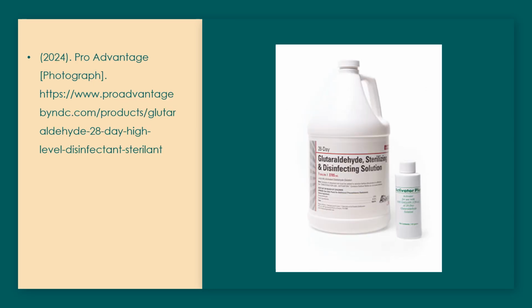Glutaraldehyde is another solution that is commonly used in cold chemical sterilization. Items for this solution must soak for 10 hours to be sterilized. This also can be used for endoscopes, cameras, and cords, but is deemed less effective due to its long period of soaking.